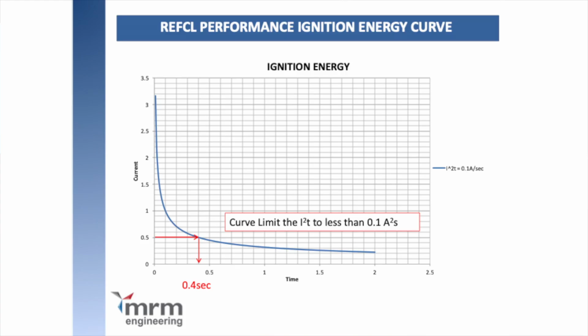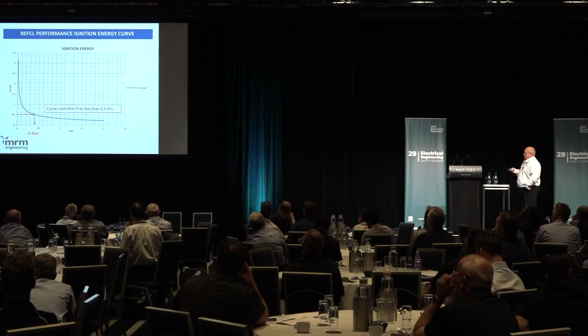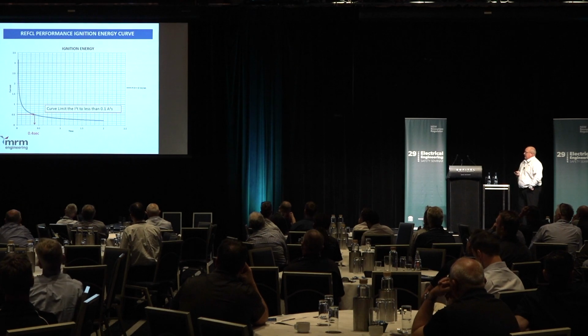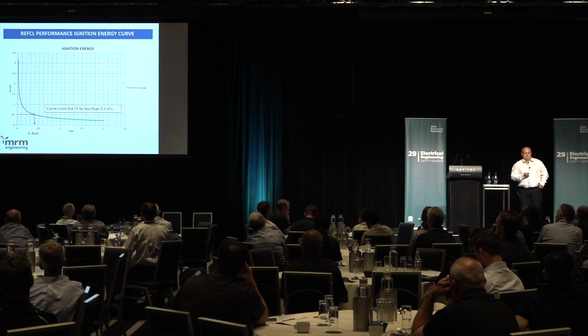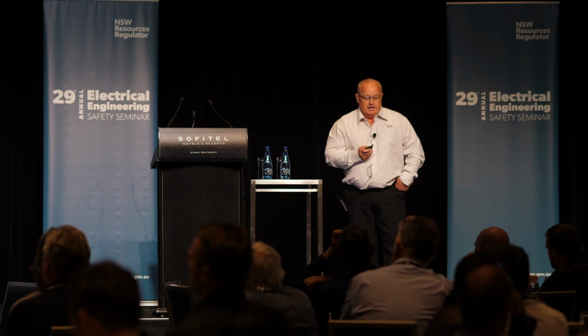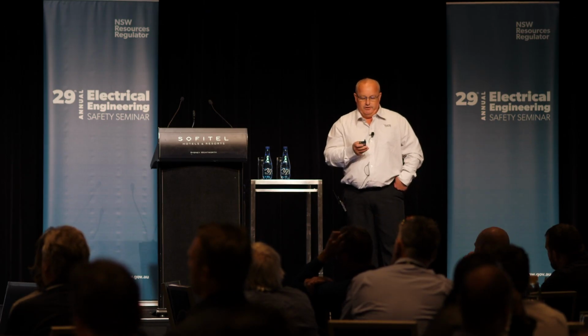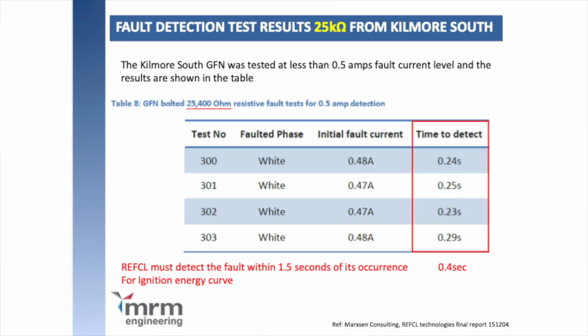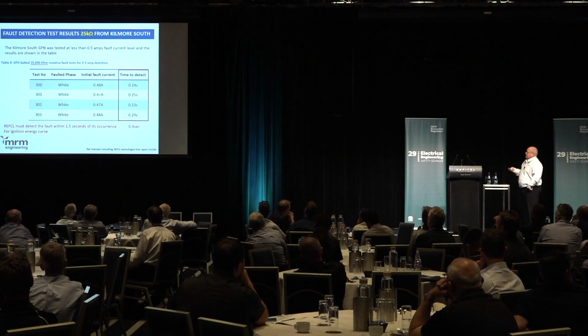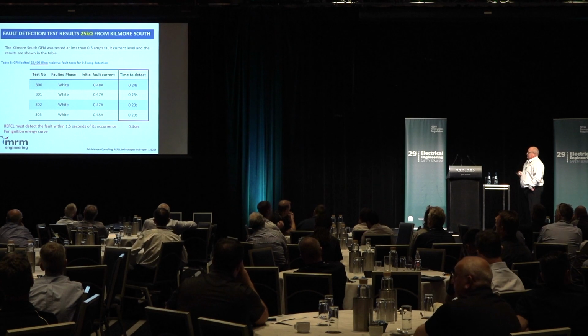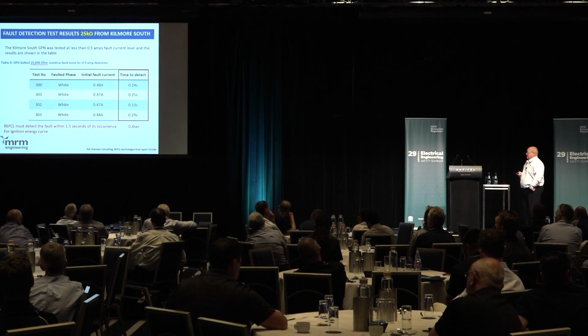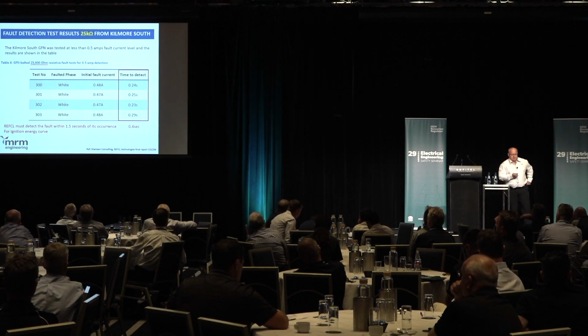So you can see here this is a graph of the ignition. On the graph, there's your I squared T, and for the 0.5, we have to operate or clear within 400 milliseconds. So their system is proposing to shut down the power within 400 milliseconds of a ground fault occurring. When they did their tests, they set the detection time at 0.5, and the clearance times they got were around 0.2 to 0.3, 300 milliseconds. So that's super quick, even for our standards, what we use on mine sites.